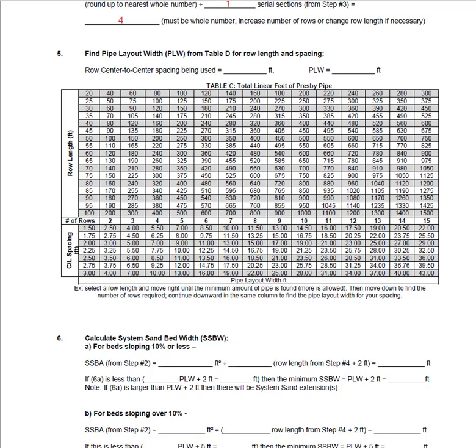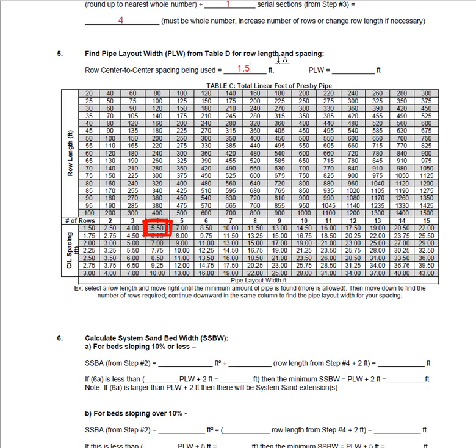We are now going to determine the dimensions of our field. In step five we will determine the pipe layout width. The upper left column of table C lists row lengths. We will locate our row length of 70 feet and move to the right until we find the total amount of pipe required — 280 feet. We then move down this column until we reach the row indicating how many rows are required, confirming our value of four, and then continue down until we are in line with our center-to-center spacing. The minimum is one and a half feet, which is what we will use. Where our chosen spacing and our row length column intersect, we find our pipe layout width of five and a half feet.